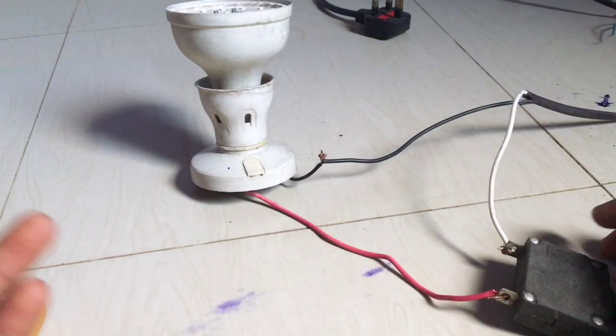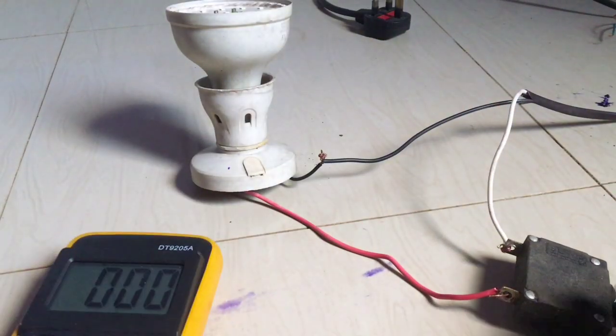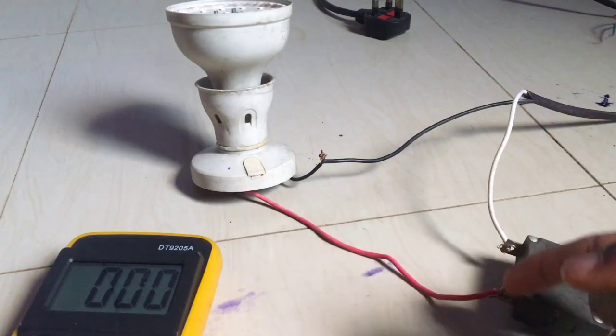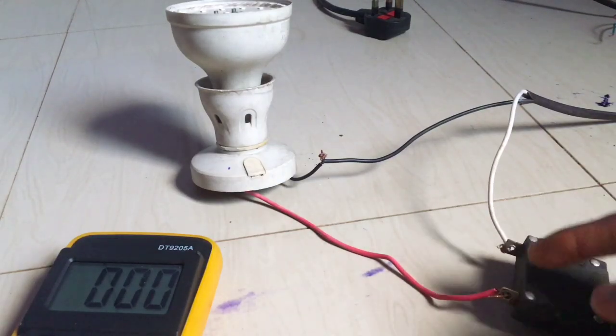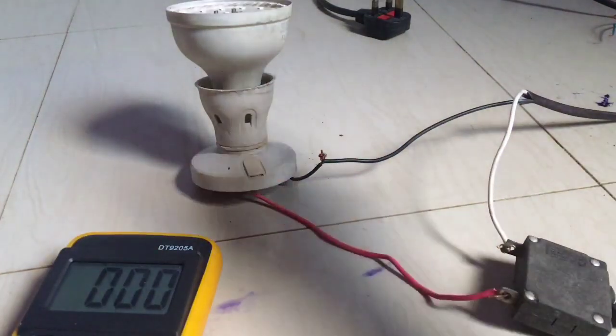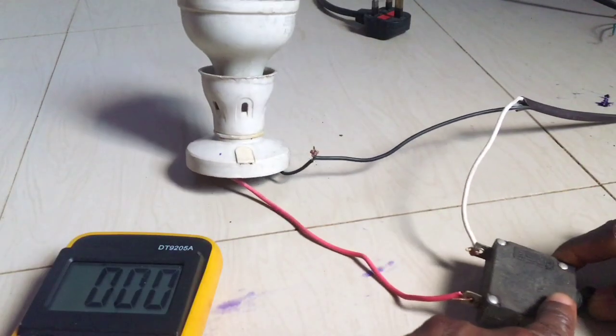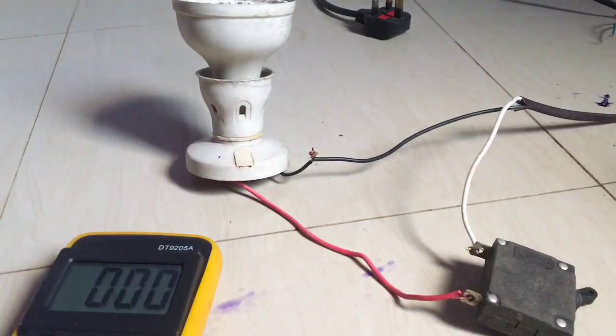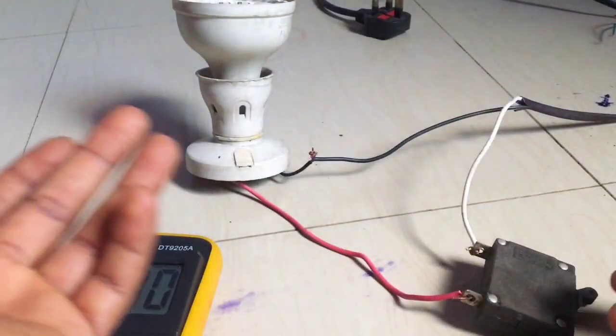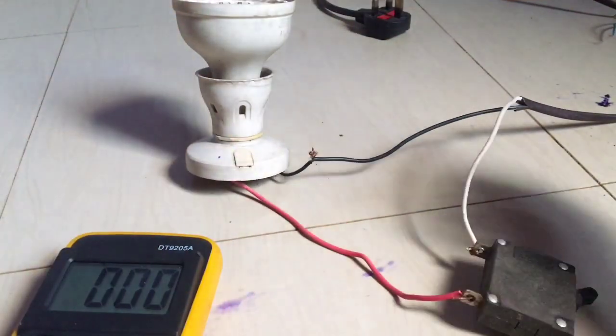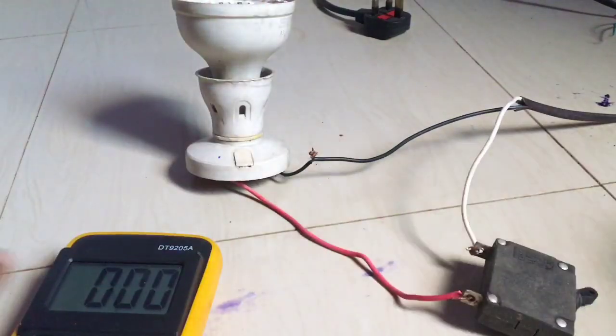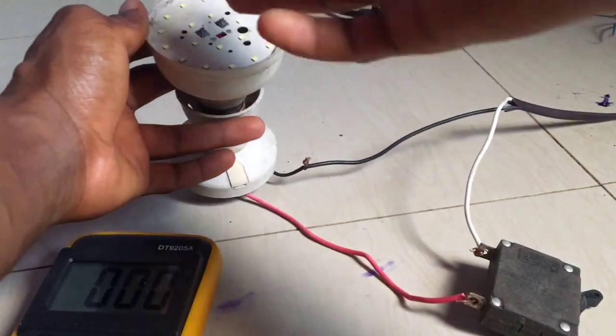All right, so remember, a switch in the off state should not give continuity between these two terminals. So if you want to read continuity between the two terminals, you have to disengage it from the supply. But when it's in the on state like this, there should be continuity between the two terminals. So this is another way to rectify if the fault of your lighting point is from the switch or not. So with this, you can always know your way around how to test for which exact fault is causing your lamp not to turn on.